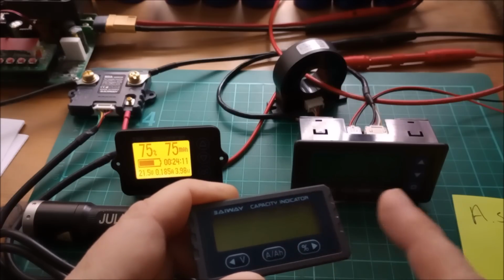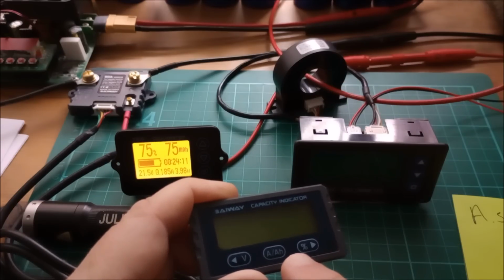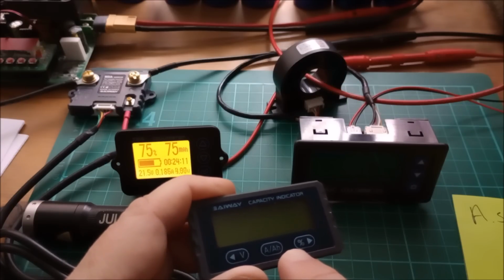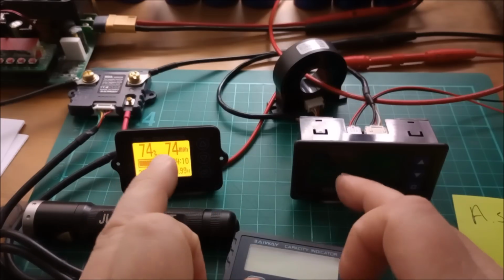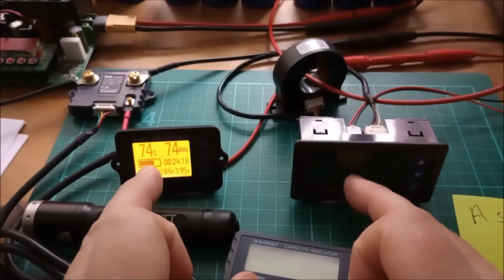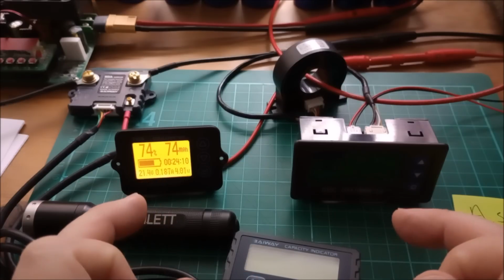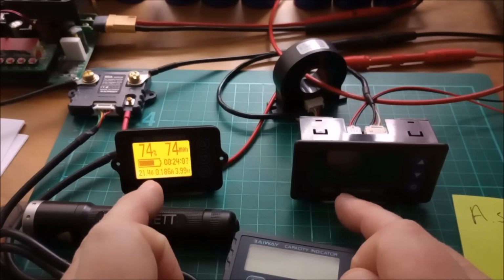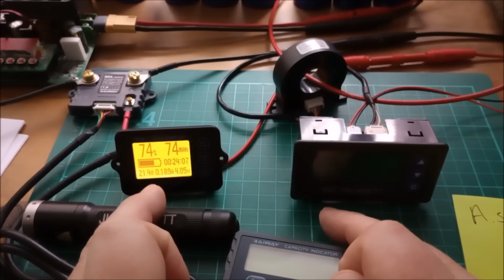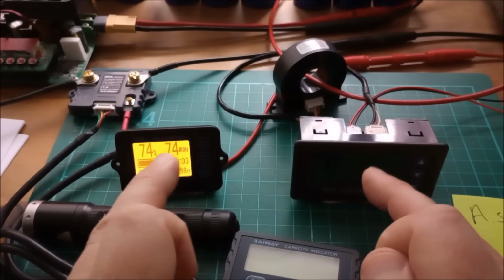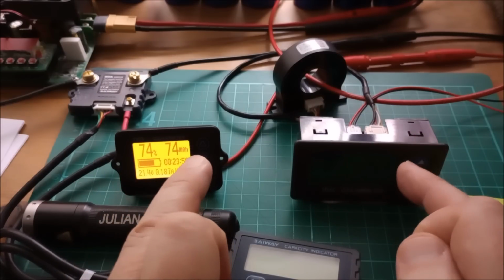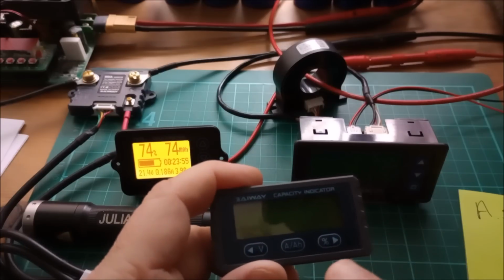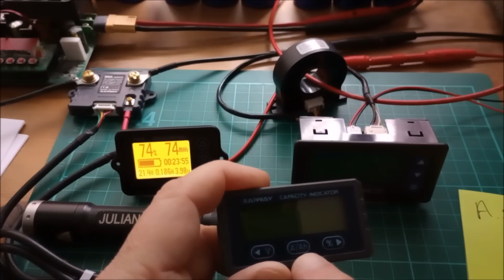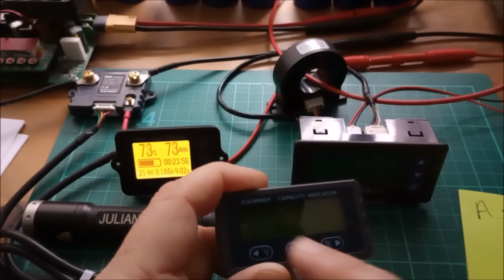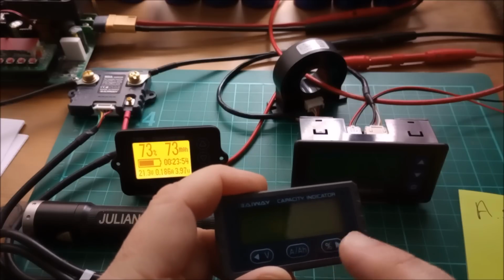And I don't think this one has the top voltage synchronizer. So both of these, the TK15 and the H56, I've set them to synchronize the 0% point at 12 volts and synchronize the 100% point at 24 volts. This one only has the low voltage synchronization point - I don't think it has the high voltage synchronization point, so it just isn't as good.